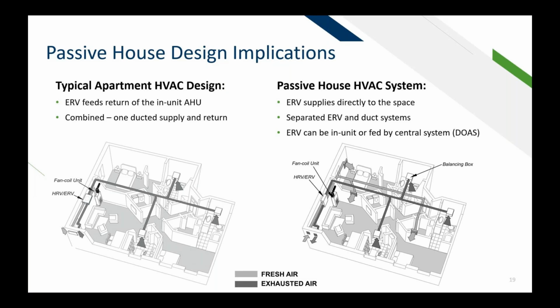So an ERV, by the way, can be in-unit or fed by a central system. Now, I've talked to plenty of engineers about this, and just about across the board, they've all said the same thing: it really just depends on the project. There's benefits to both. One of the big benefits to having an ERV inside the unit is that the owner can bill the tenant individually for the electric used by that ERV. However, one of the downsides is that now you have more penetrations in the outside of the building, and you have to pass that leakage test at the end, which is very strict, more strict than the HERS rating. So it could be beneficial to have a central unit like a DOAS unit, but then you have to worry about some of the riser implications like fire barriers, smoke dampers, etc.